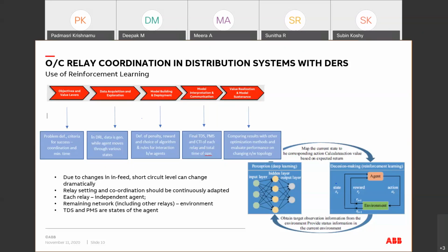Now, the penalty and reward at each time step is given based on the maintainability of the coordination time interval between the primary, backup, and tertiary relays, along with the constraint that the overall time of operation should be minimum. So this is how you are turning the coordination problem into a reinforcement learning environment problem. Each relay continues to tinker with its time dial and plug multiplier setting during the training process, and determines the optimum action which will be needed to ensure it gets the maximum reward.